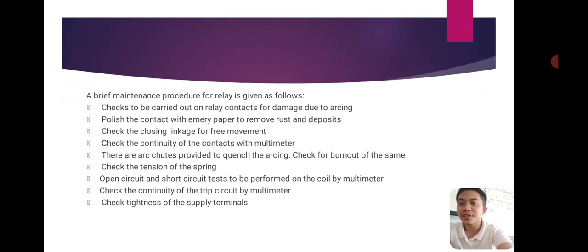A brief maintenance procedure for relay is given as follows. Check the relay contacts for damage due to arcing. Polish the contacts with emery paper to remove rust and deposits. Check the closing linkage for free movement. Check the continuity of the contacts with a multimeter. There are arc chutes provided to quench the arcing. Check for burnout of the same.